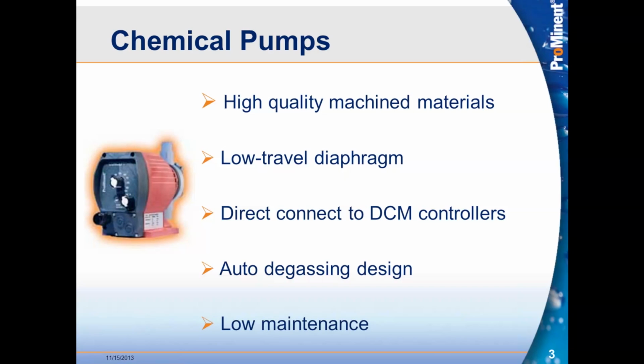And the reason being is that on a Stenner pump, since it's a peristaltic pump, it has a peristaltic tube. That peristaltic action requires the tube to compress all the way flat and then rebound to its full round condition. Well, after a while, that tube loses the elasticity and does not rebound to full diameter, and so we lose pumping capacity. So it's quite possible with worn tubes in some of these pumps on pools that run a lot of product through, that they can start to have problems that imitate controller problems because the pump isn't keeping up with the requirements for dosing because it's lost some of its capability through worn tubes. So we can tell people that we don't have that problem.